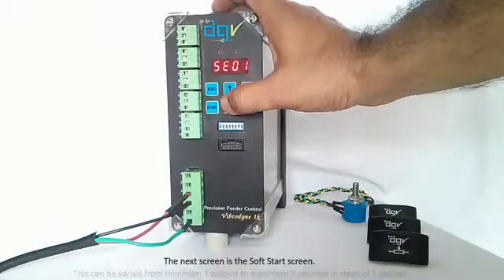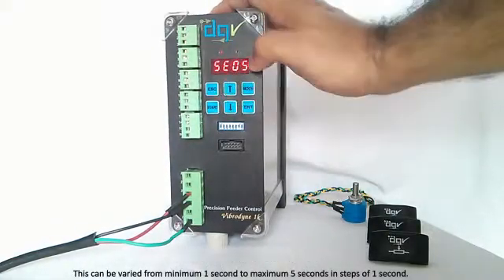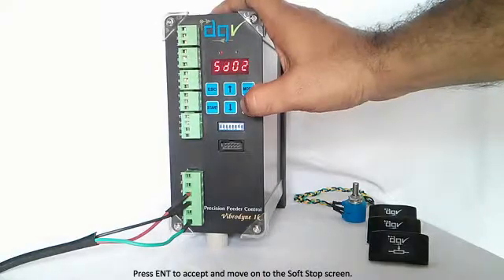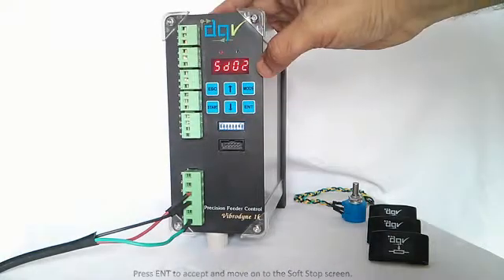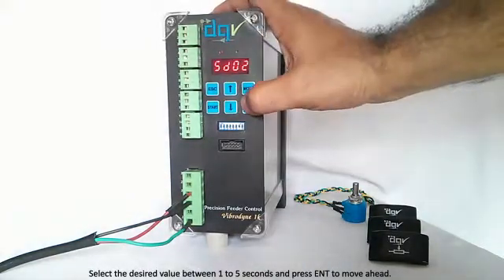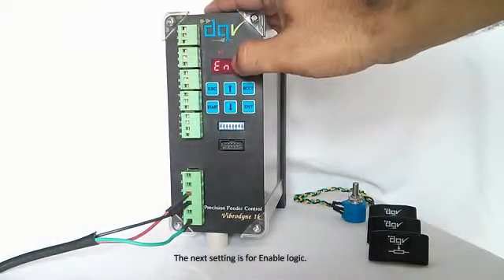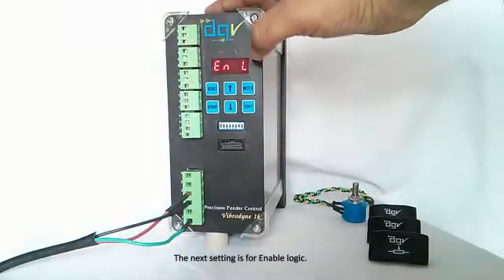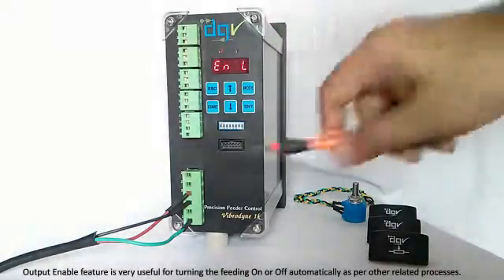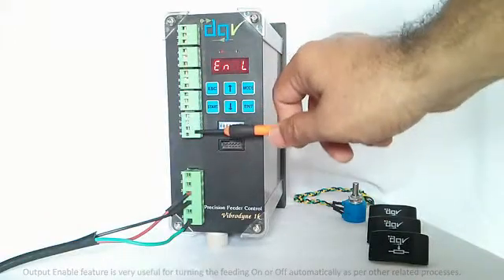I am setting the frequency at 50 Hz and pressing Enter. Next is soft start — currently 2 seconds. I can bring it down to a minimum of 1 second or up to a maximum of 5 seconds. I am setting soft start at 4 seconds and pressing Enter. This is the soft stop value — whether your controller output will actually go to 0. I press Enter and come to the enable logic screen.